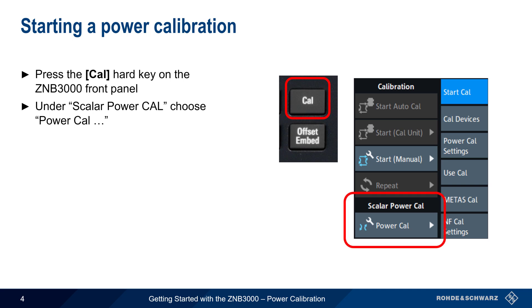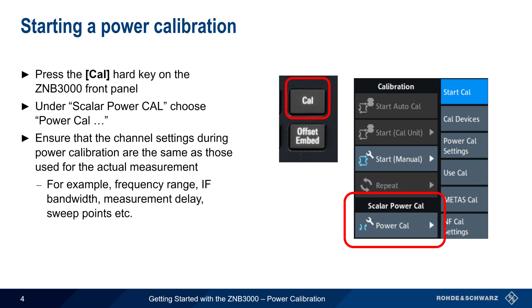To start a power calibration on the ZNB3000, press the Cal hard key on the front panel, and then select Power Cal from the Calibration menu. It's important to ensure that power calibration is done using the same channel settings as those used for the actual measurement. Parameters such as frequency range, IF bandwidth, and number of sweep points should be configured to match those used during post-calibration measurements. Changing any of these parameters after a power calibration has been completed may result in a reduction of measurement accuracy.